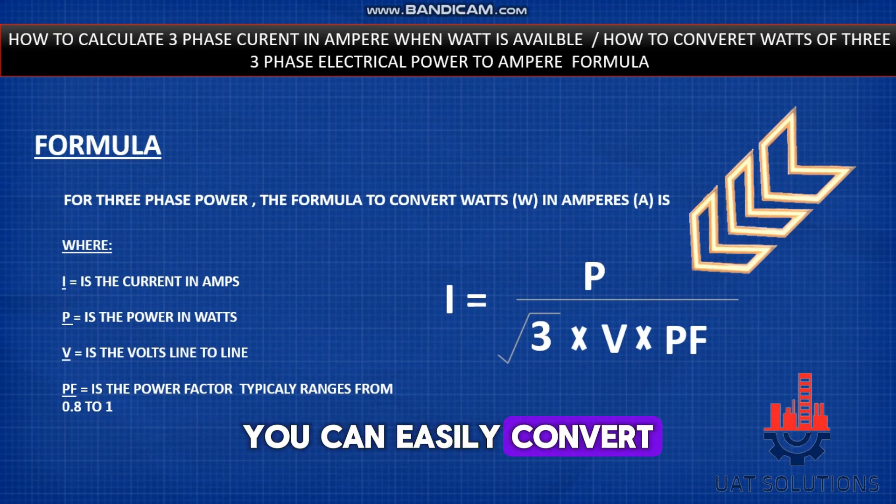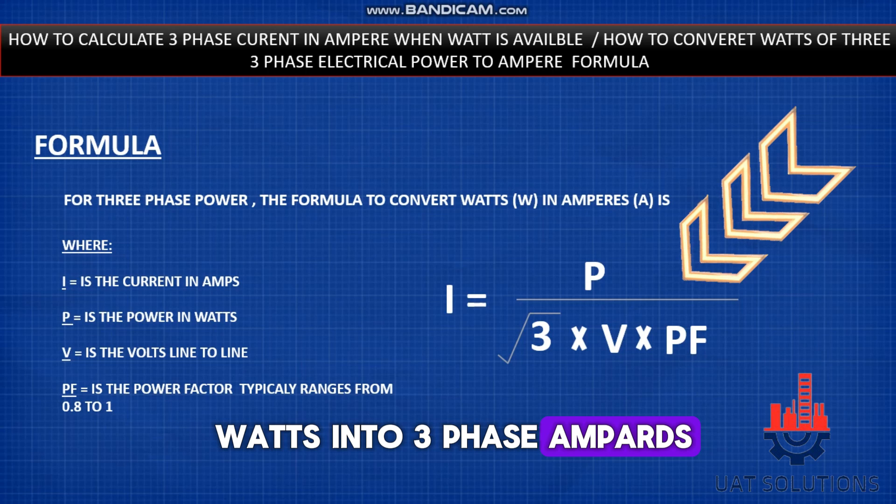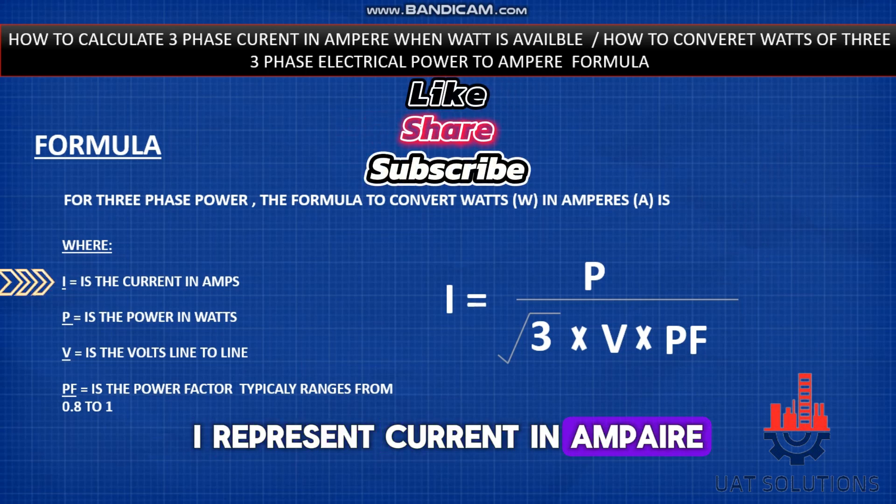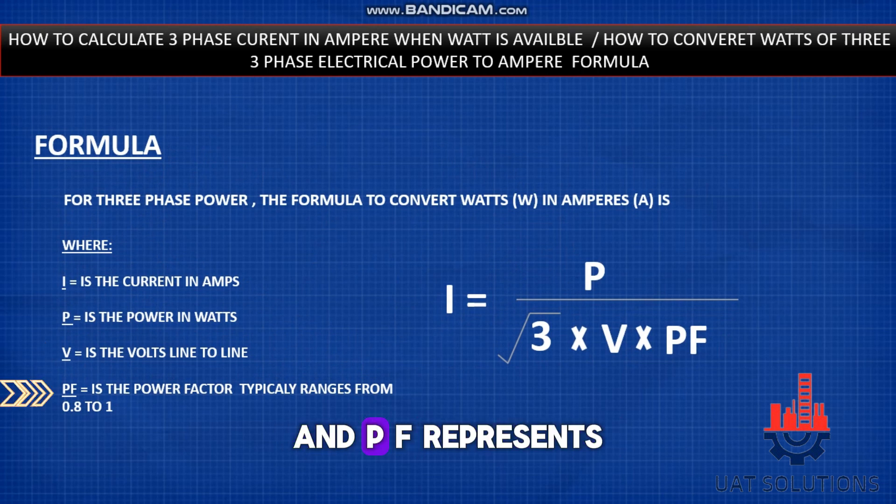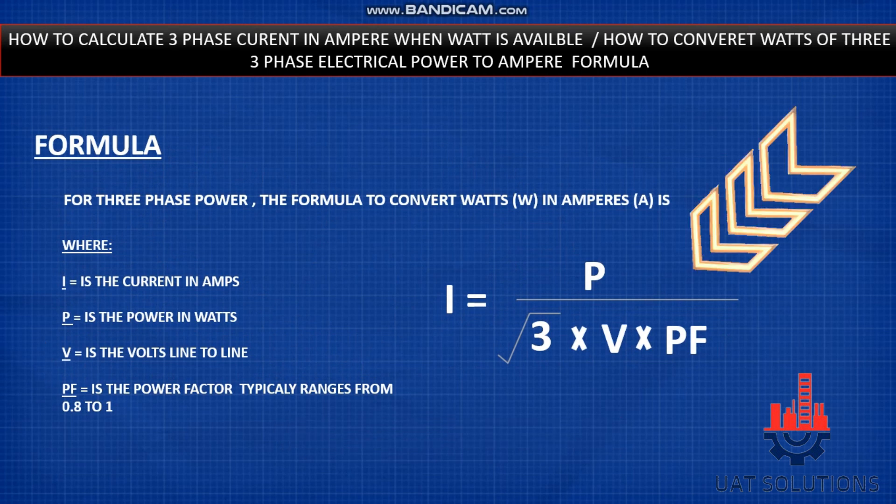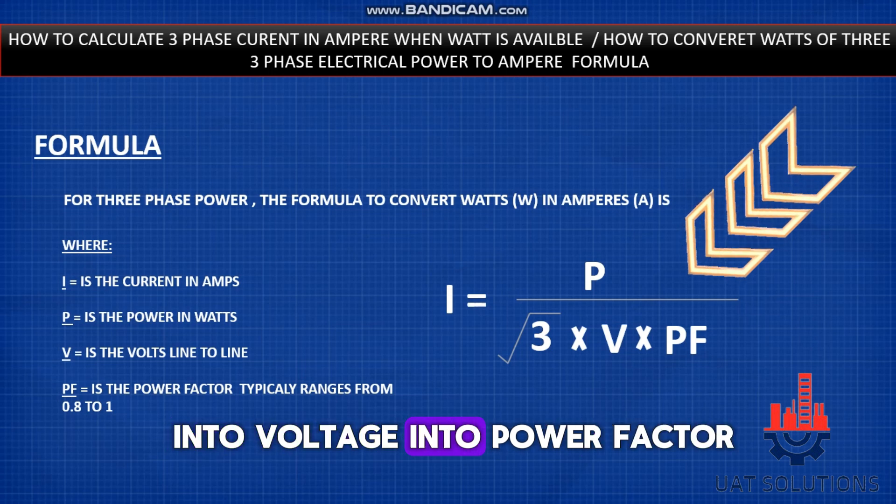Using this formula, you can easily convert watts into three-phase amperes. I represents current in amperes, P represents power in watts, V represents line-to-line voltage, and PF represents power factor. The formula is: I = P / (√3 × V × PF).